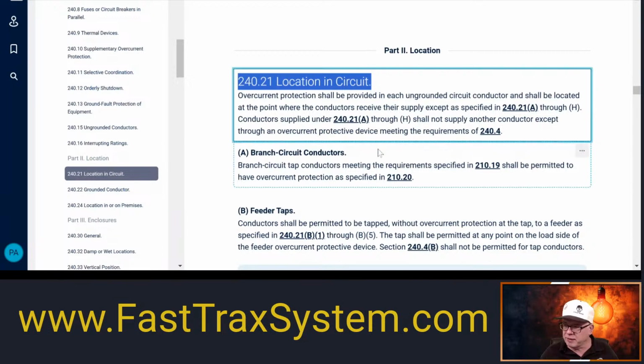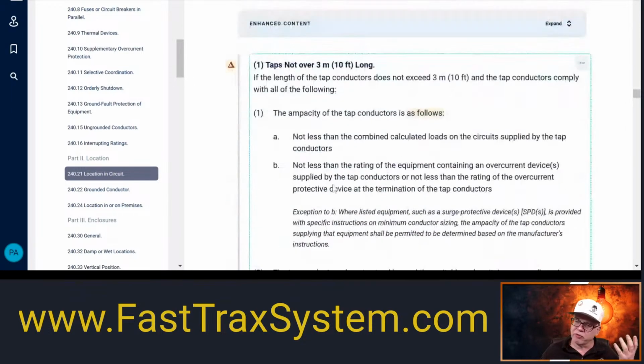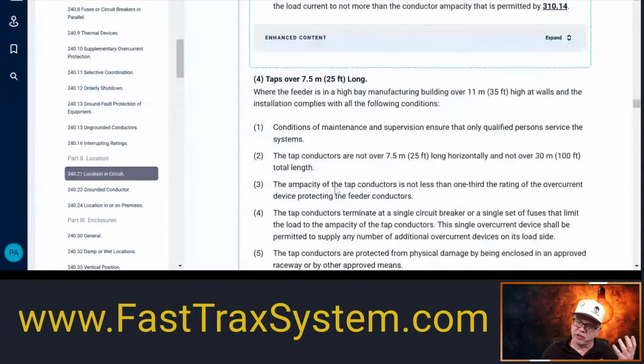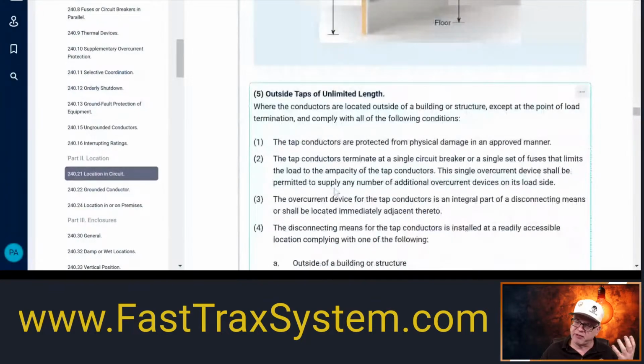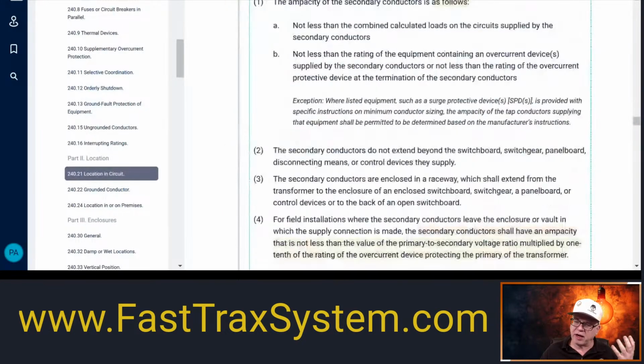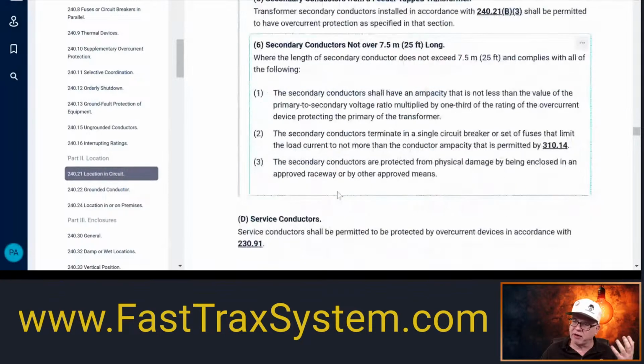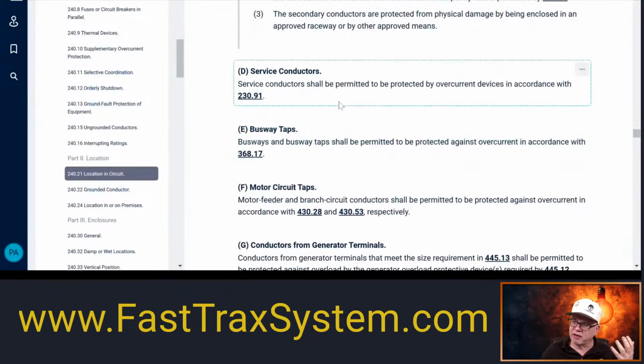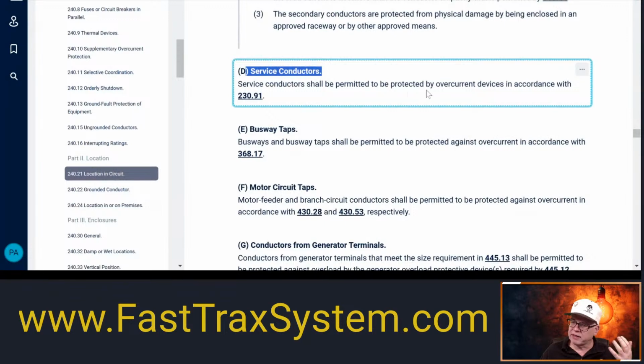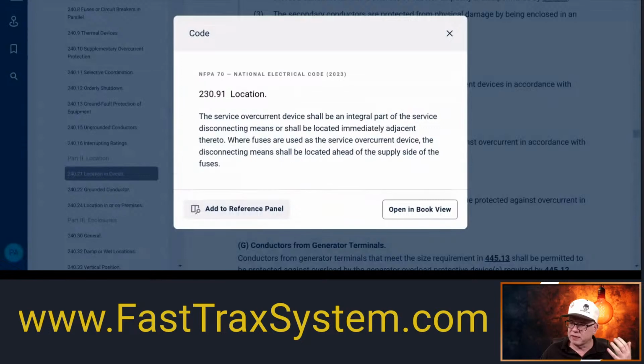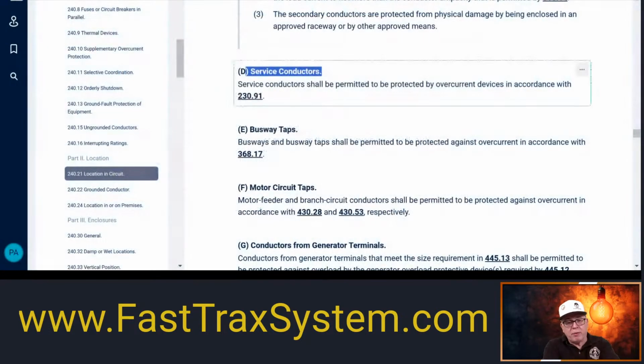But there are some allowances, and here's what we've been dabbling in and looking at: the different tap rules, different secondary conductor rules. Is that all that's there? No. There are applications down here where it says service conductors shall be permitted to be protected by overcurrent devices in accordance with 230.91. So we do have some applications there. And it's also important to remember that in many cases, you're allowed to do certain things like, remember service conductors?